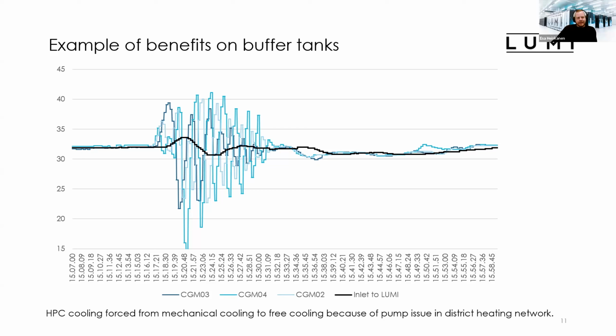But this black line indicates the measured temperature after the buffer tanks, and as you can see, it balanced these swings pretty well. And this is the worst case that I have seen in this cooling. So it was very reasonable to install these buffer tanks on the outlet side, on the inlet side of the cooling loop for the HPC. So the variation for the Lumi only ended up a little bit over 33 degrees, and then it went to about 31 degrees, and then it was balanced at 32 degrees with this set point.